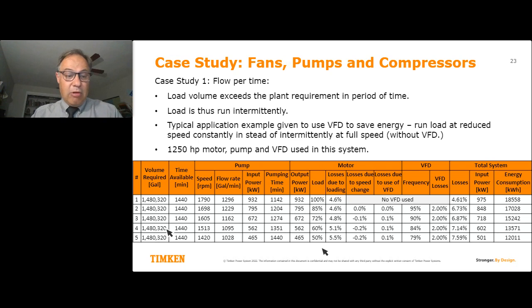I can see the pump only needs to run. Sorry, that was a typo. Now, the pump runs full time. In other words, I don't switch it on and off. Now, the pump at 1420 RPM only consumes 465.